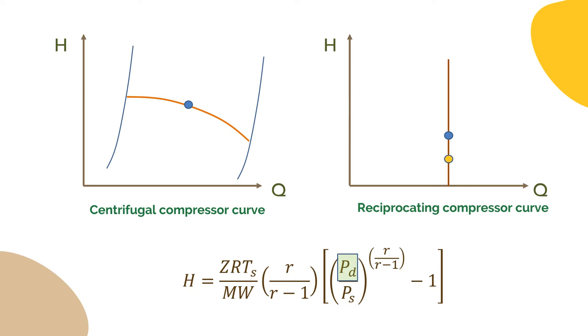So when the suction temperature increases at a constant head, the compressor will give less discharge pressure. While when we have a gas of a higher molecular weight, the compressor will give a higher discharge pressure at a constant head.